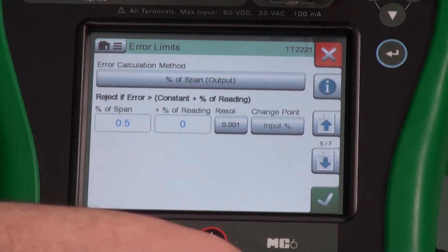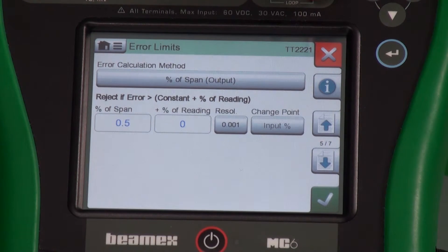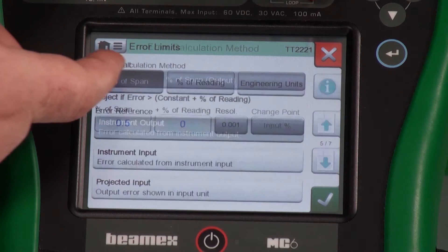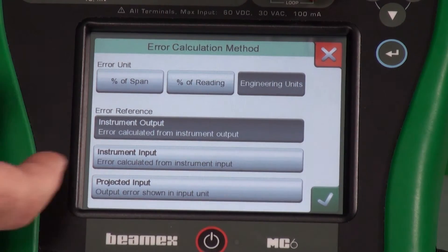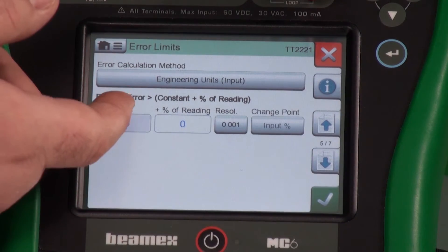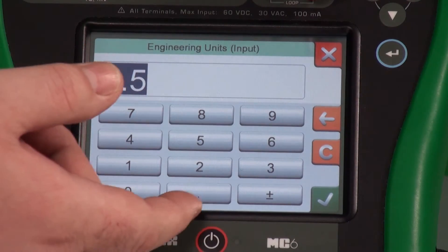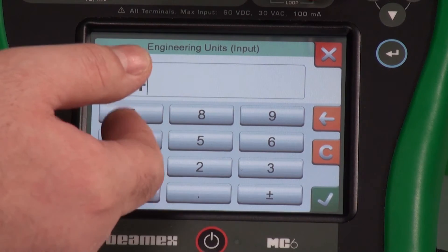Stability check means that we have a stable signal — it's not noisy or drifting up or down, but it is flat and stable. The error tolerance default is a half a percent of span. But maybe you want it to be plus or minus half a degree or a quarter of a degree. We just change our error calculation method, change it over to engineering units. Maybe I want this to be plus or minus 0.4 degrees.